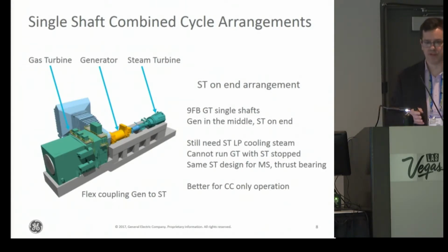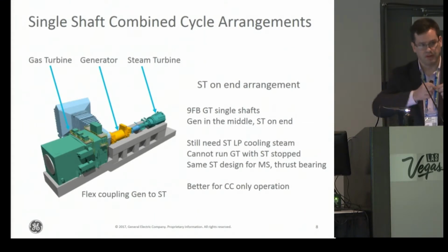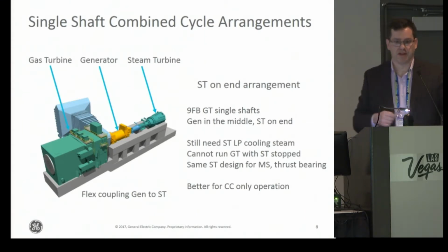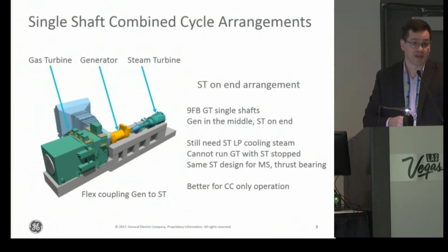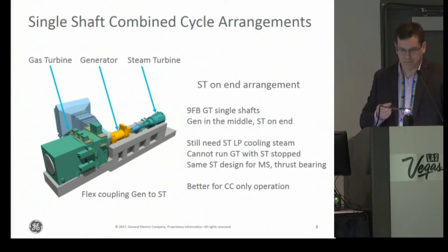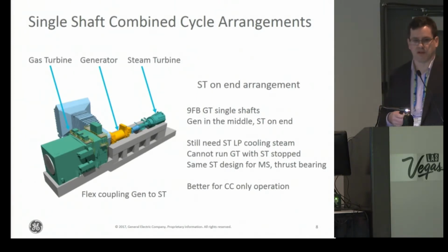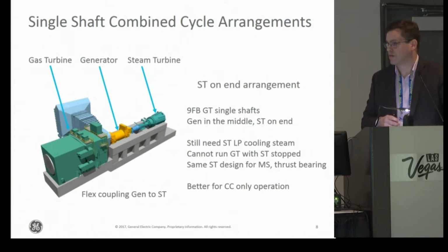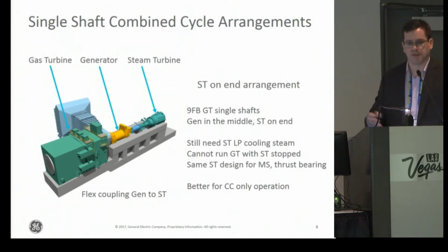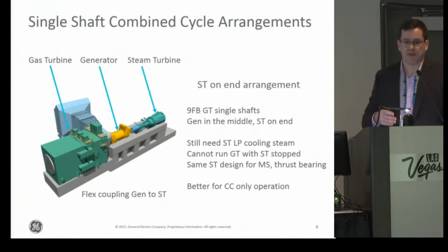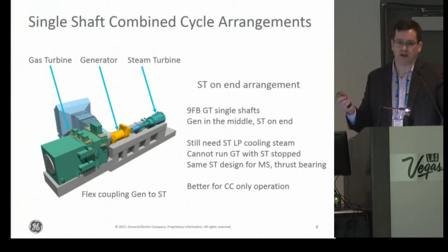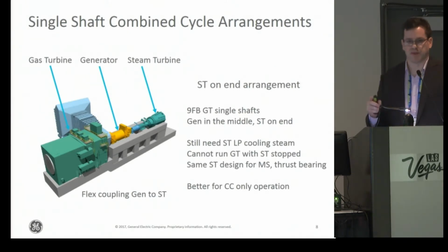Now you have to move the generator, or find some way to pull that long field out of the generator internals so you can do maintenance on it. But this also allowed us, with the axial exhaust steam turbine, to just put a condenser on the end of the building, giving a very low centerline and low cost of construction. It solved some problems we had with the steam turbine in the middle, but it also created some issues of its own.